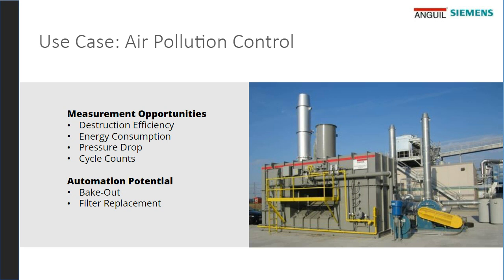There's a whole host of things, like heat exchangers, whether on regenerative units with ceramic media or metallic heat exchangers, for plugging and degradation. Look at thermocouples, valves, sequencing, number of times valves move, number of cycles, gas meters, electric meters. It's endless what we can monitor if the equipment's there, supported by the companies and the workers on staff.